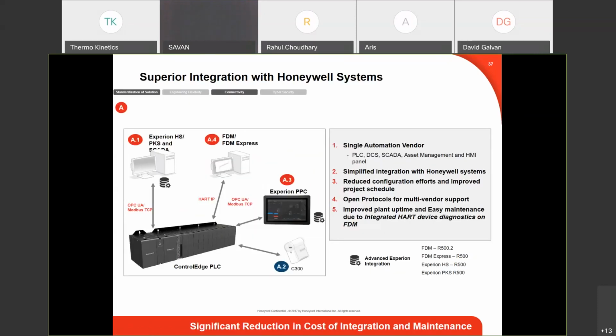The integration into Experion PKS, HS, and LX is via OPC UA. We also have CDA. For those of you who are familiar with controller data access, we do have CDA ability. So you have OPC UA, we have CDA, and then we also have Modbus TCP. If you just want to connect it via Modbus, we have that ability as well. Very powerful stuff.